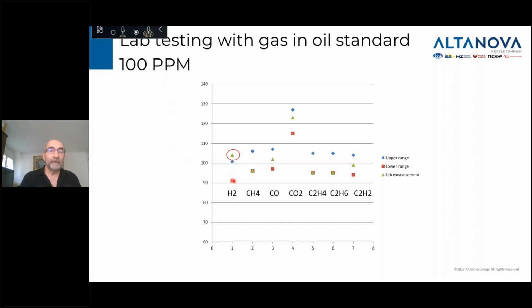The blue and the red square are the range of that gas, based on the spec plus or minus 5%. And the green triangle is the measurement. On this GC, you can see that for all the gases except hydrogen, they're measuring exactly the amount of gas in that oil sample, except a little bit on the hydrogen, where they measure slightly higher.